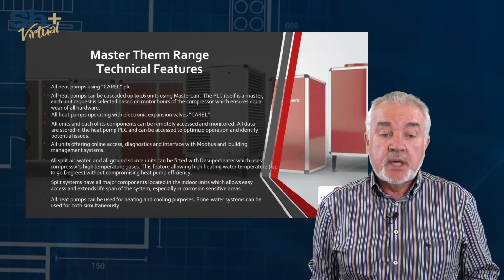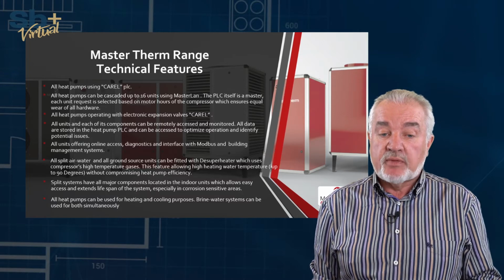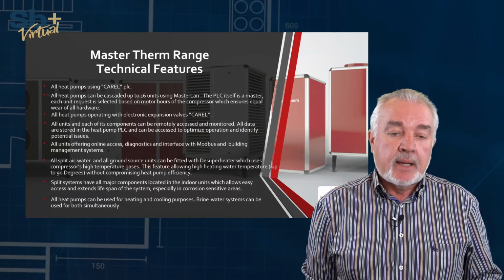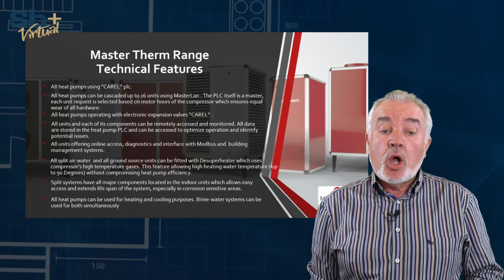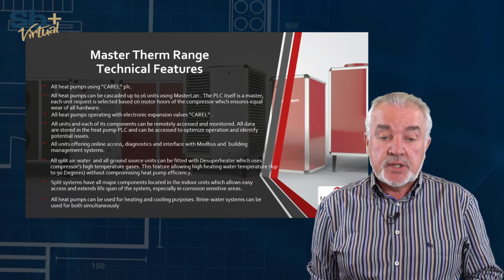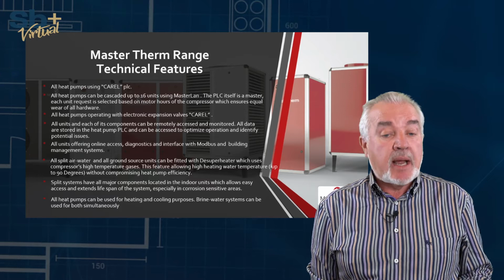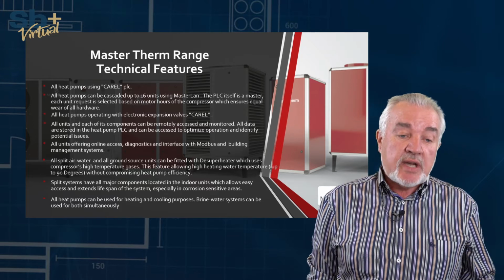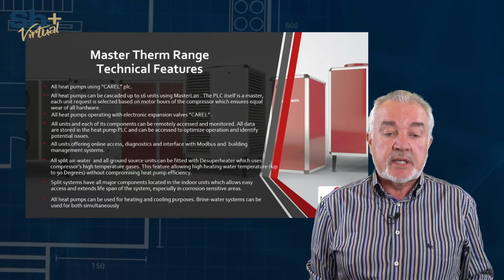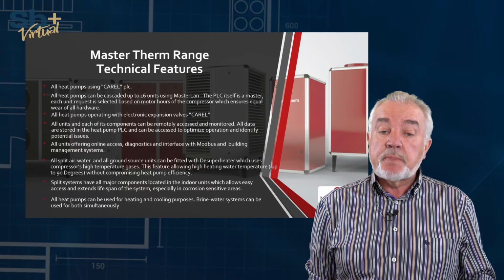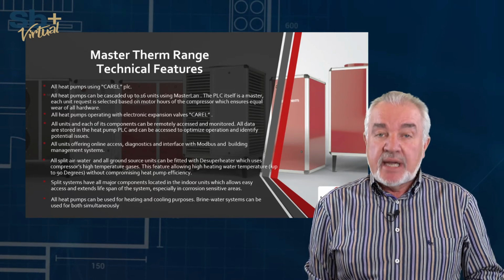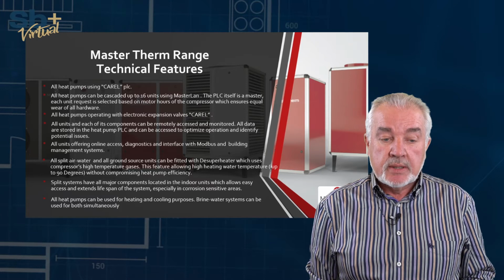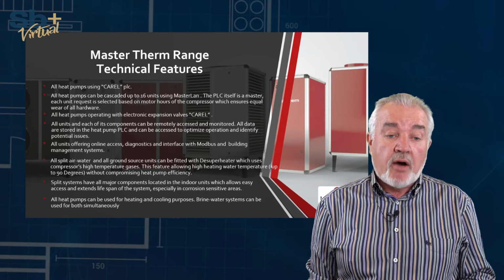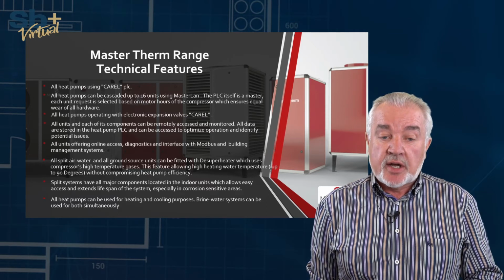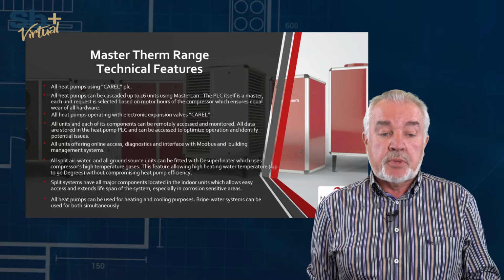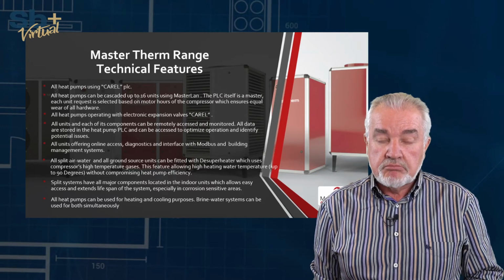All of our heat pumps operate with an electronic expansion valve, again a Carel part. All units and each of its components can be remotely accessed and monitored. So all of the data are stored in the heat pump PLC and can be accessed to optimize operation and identify potential issues. All units offer online access, diagnostics and interface with Modbus and building management systems.